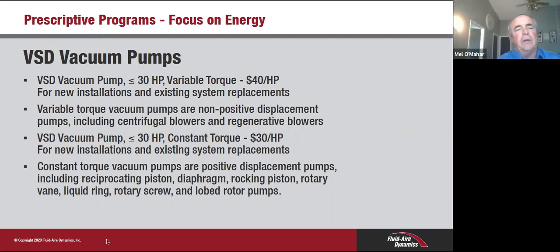Yeah. Focus on Energy is now covering VSD vacuum pumps with variable speed. They realized it's getting a little more popular with manufacturing where people need vacuum in their facility. I've also found that vacuum is very up and down at a lot of facilities. They may run vacuum for 30 minutes and then stop. Things like that can really be helped by a variable speed vacuum unit, and with varying demands too. So it's a good energy saver as far as saving power.